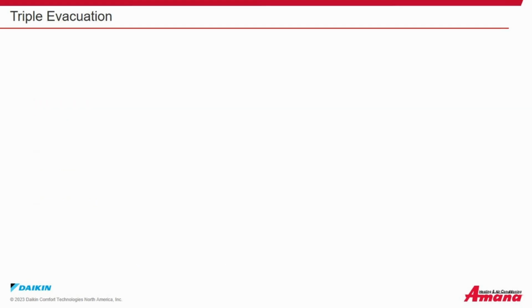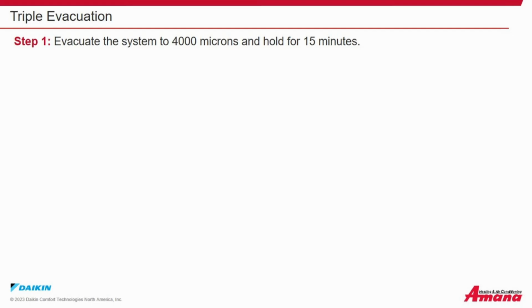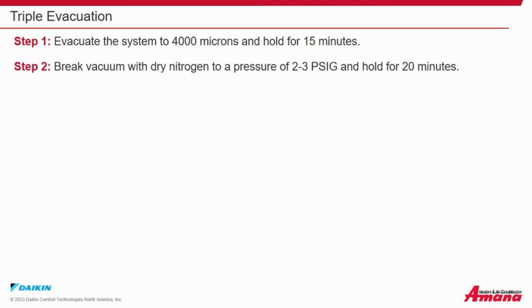Next, perform a triple evacuation. Triple evacuation is the only way to ensure that your system is dry. Step 1. Evacuate the system to 4,000 microns and hold for 15 minutes. Step 2. Break the vacuum with dry nitrogen to a pressure of 2 to 3 psig and hold for 20 minutes. Step 3. Evacuate to 1,500 microns and hold for 20 minutes.